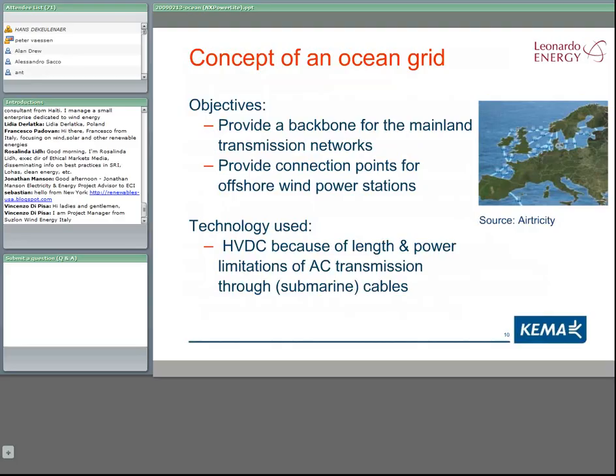Then there is another problem. If you think about classic HVDC with thyristors, thyristors can only be switched on, so the switch off happens during natural current zero. If you have to reverse the power flow, you have to reverse the voltage, and that's a very severe stress for cables. For that reason, classical DC power cables are often what's called mass impregnated, heavy, with oil and mass insulation capable of dealing with those voltage switches, those polarity reversals.